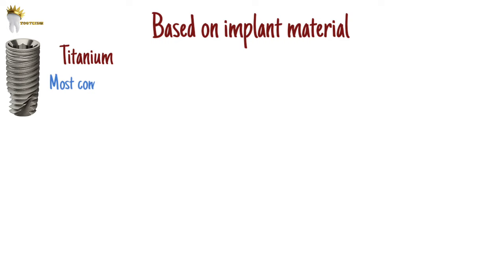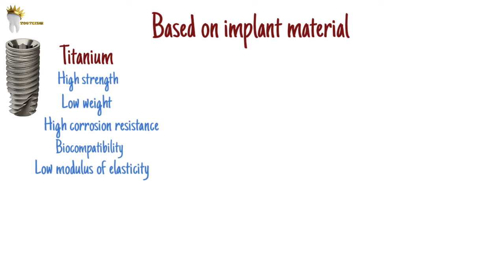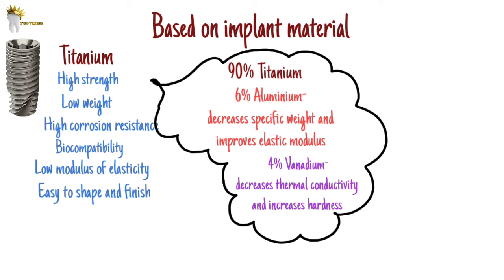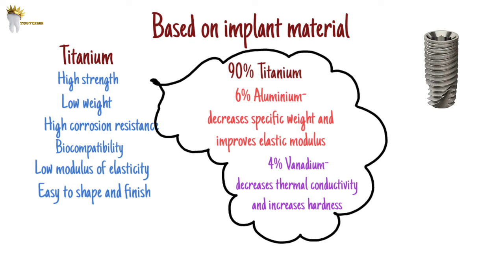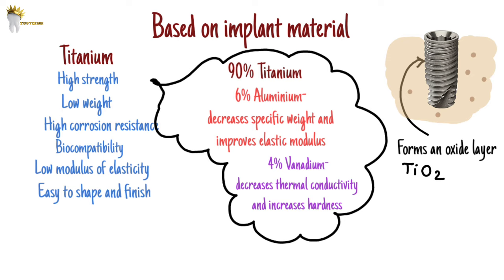On the basis of implant material, we have titanium alloy implants and zirconium implants. Most root form implants currently used are made of pure titanium or titanium alloys. Titanium offers high strength, low weight, high corrosion resistance, biocompatibility, low modulus of elasticity, and easy shaping and finishing capability. The most frequently used titanium alloy has 90% titanium, 6% aluminium (which decreases specific weight and improves elastic modulus), and 4% vanadium (which decreases thermal conductivity and increases hardness). When exposed to air, titanium or its alloy immediately forms an oxide layer — titanium dioxide — over its surface, which plays an important role in corrosion resistance, biocompatibility, and osseointegration.